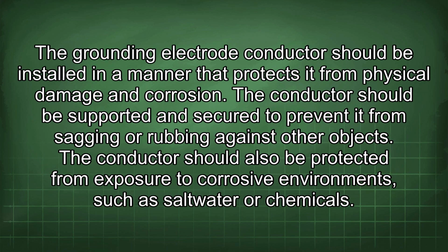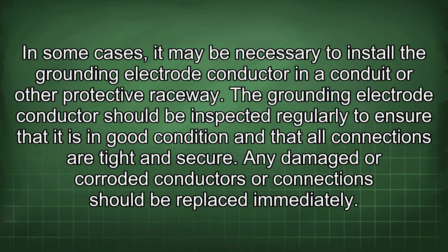The grounding electrode conductor should be installed in a manner that protects it from physical damage and corrosion. The conductor should be supported and secured to prevent it from sagging or rubbing against other objects. The conductor should also be protected from exposure to corrosive environments such as salt water or chemicals. In some cases, it may be necessary to install the grounding electrode conductor in a conduit or other protective raceway. The grounding electrode conductor should be inspected regularly to ensure that it is in good condition and that all connections are tight and secure. Any damaged or corroded conductors or connections should be replaced immediately.